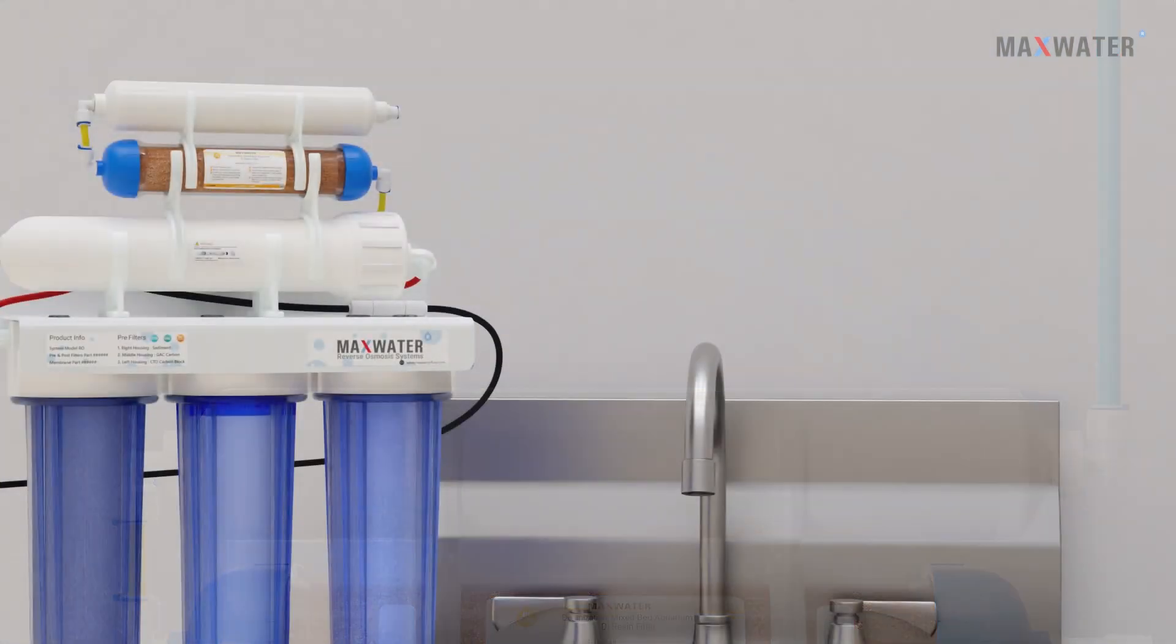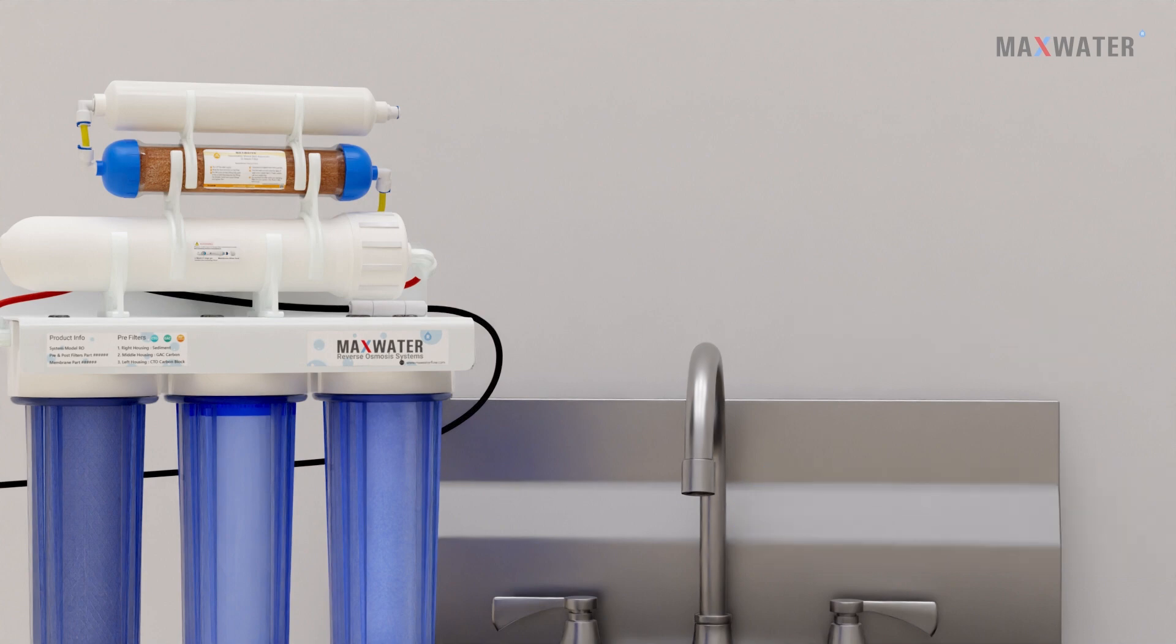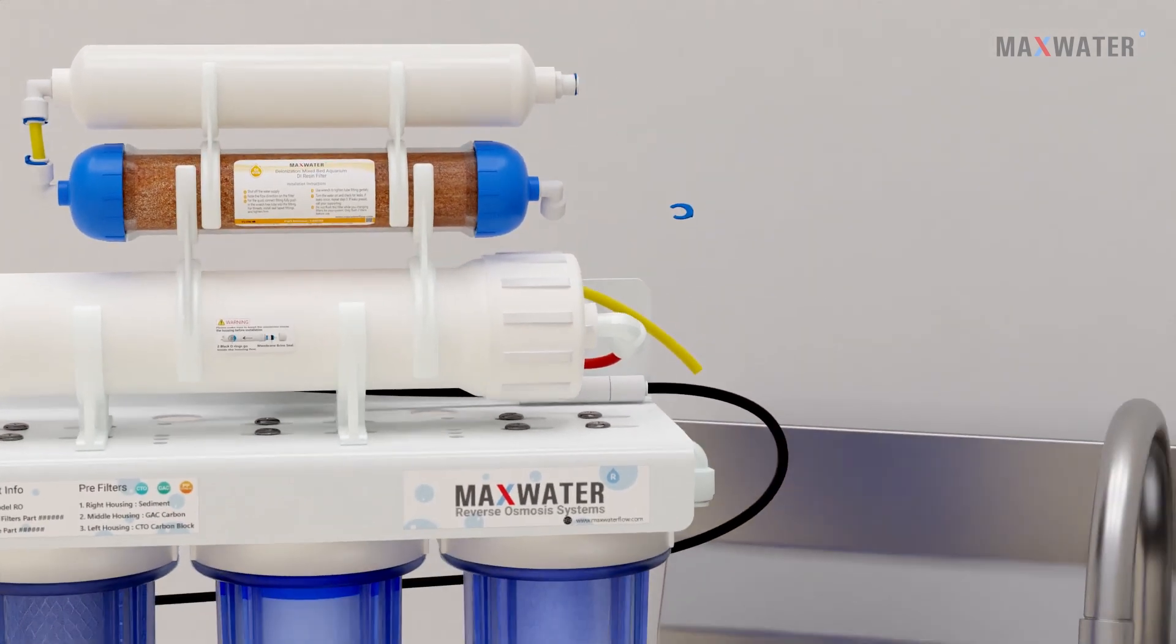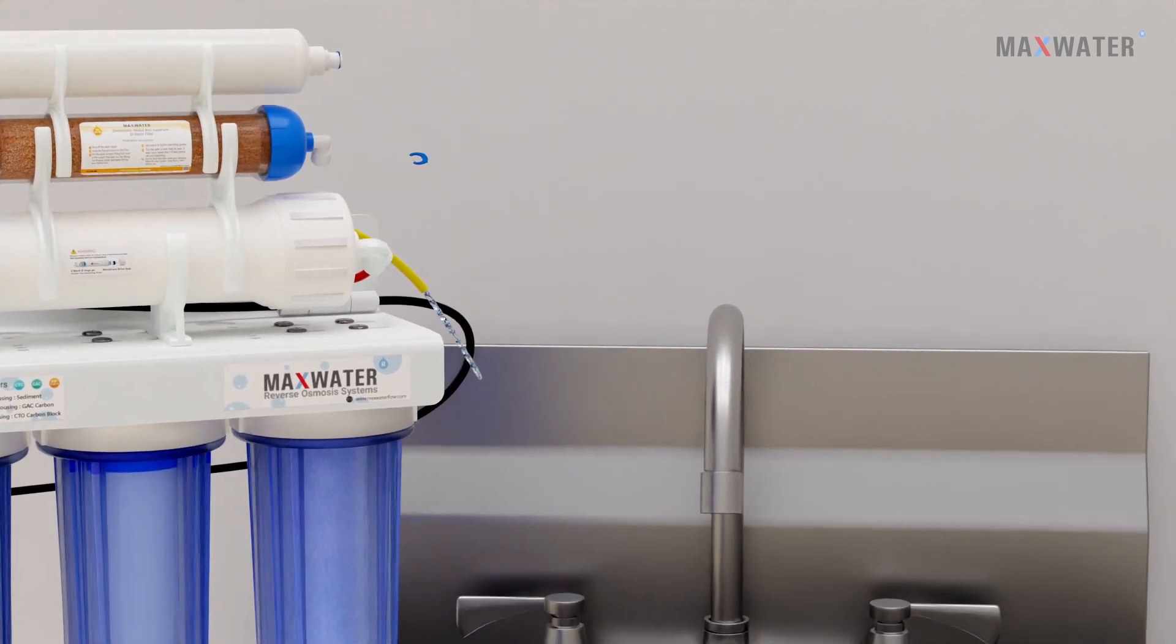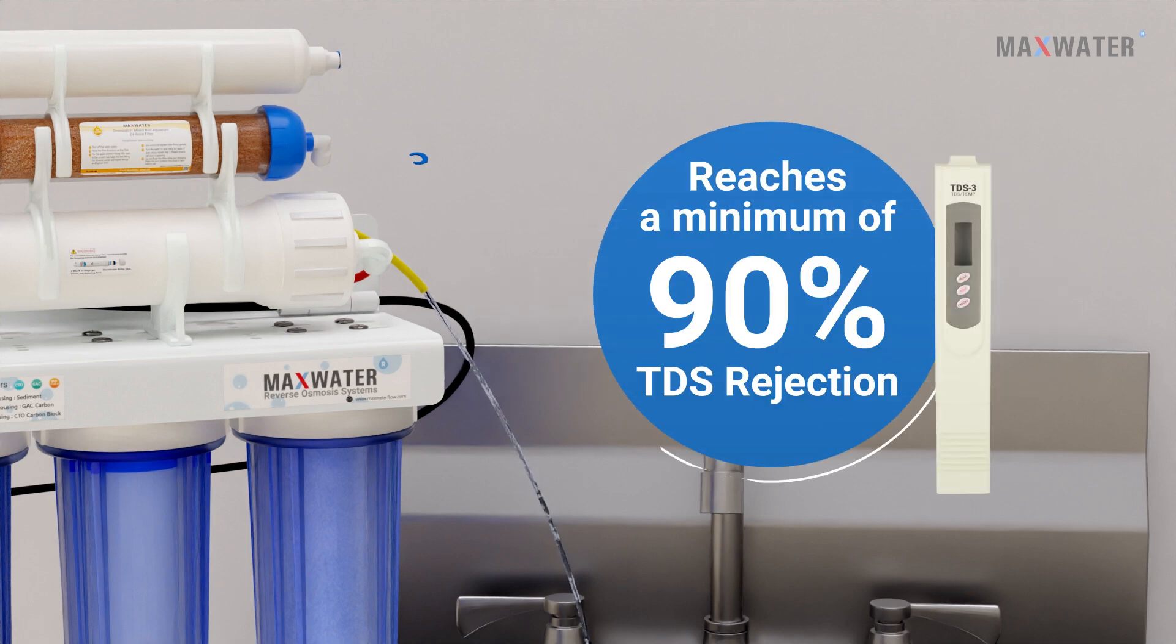Flushing step number two: RO membrane flushing. While the main water supply is off, disconnect the yellow tube from the inlet fitting of the DI filter. Place it over the sink or container to catch the water. Turn on the water supply and keep it running for at least five to ten minutes. If you have a TDS meter, keep it running until it reaches a minimum of 90% TDS rejection.